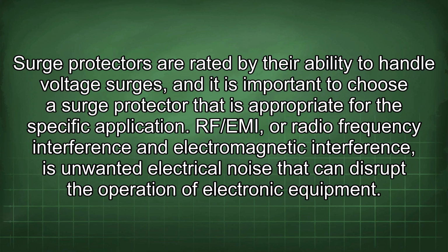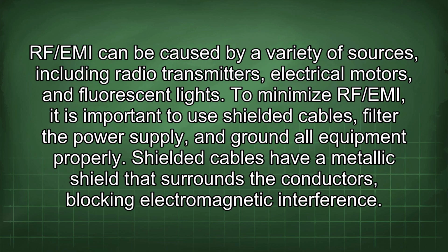RF/EMI, or radio frequency interference and electromagnetic interference, is unwanted electrical noise that can disrupt the operation of electronic equipment. RF/EMI can be caused by a variety of sources, including radio transmitters, electrical motors, and fluorescent lights. To minimize RF/EMI, it is important to use shielded cables, filter the power supply, and ground all equipment properly. Shielded cables have a metallic shield that surrounds the conductors, blocking electromagnetic interference.